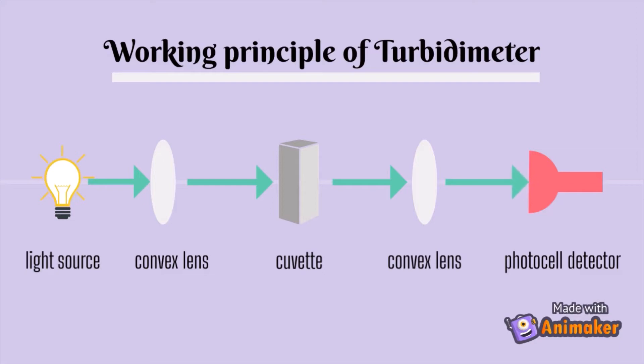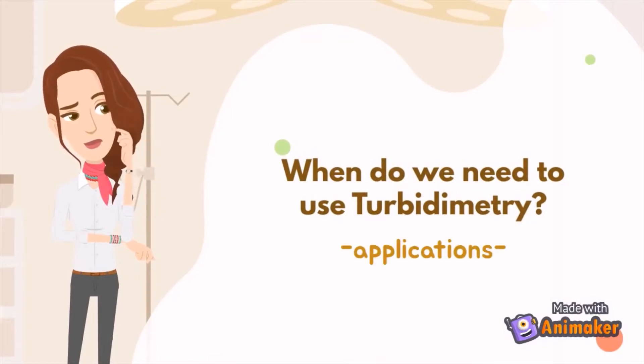A beam of light from the light source will pass through the convex lens. This incident light then travels parallel to the cuvette. The particles in the cuvette will scatter the light beam and then transmit the light to another convex lens. The light beam will be collected on the photocell detector, which will produce a current, and the result will then be displayed on the read-out meter.